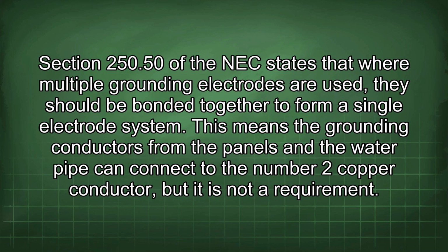Section 250.50 of the NEC states that where multiple grounding electrodes are used, they should be bonded together to form a single electrode system. This means the grounding conductors from the panels and the water pipe can connect to the number 2 copper conductor, but it is not a requirement.